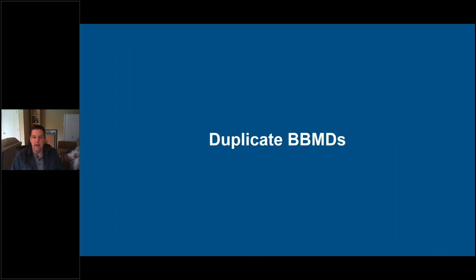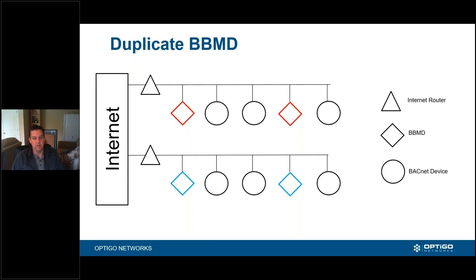The next topic is duplicate BBMD. With a duplicate BBMD, your entire backend system will still run, but what happens is you're going to have more than one BBMD on a given network — the diamond boxes in the diagram indicate a BBMD. Normally, you use a BBMD to cross different switches so you can relay information like a who-is and an I-am response between two different networks across a switch — you're basically relaying broadcast information. A duplicate BBMD means you have a second BBMD on that network, which doubles the amount of traffic.